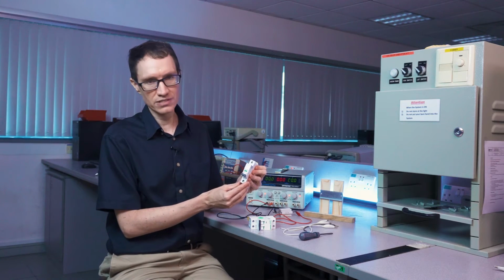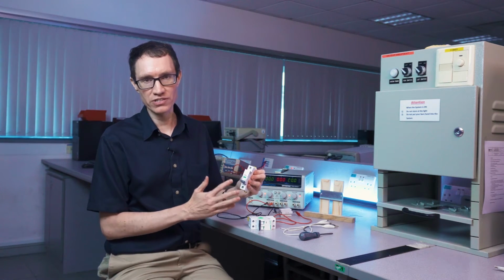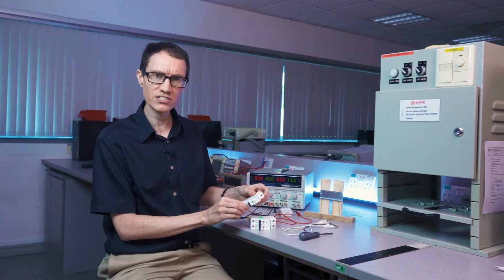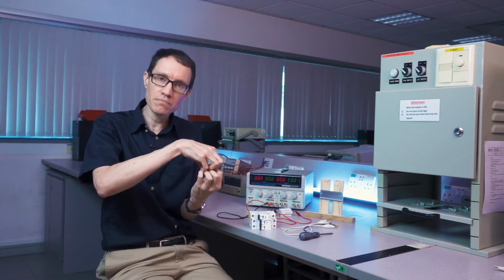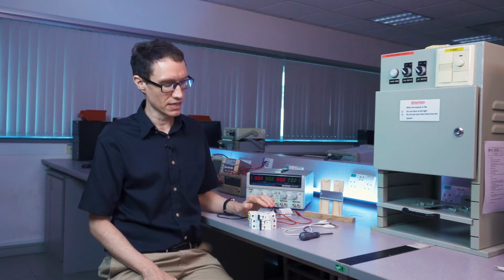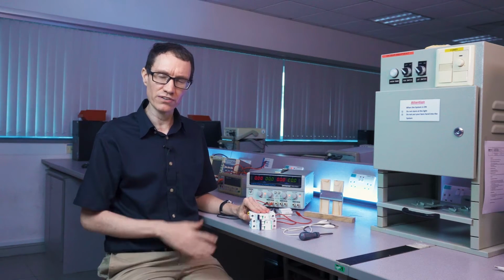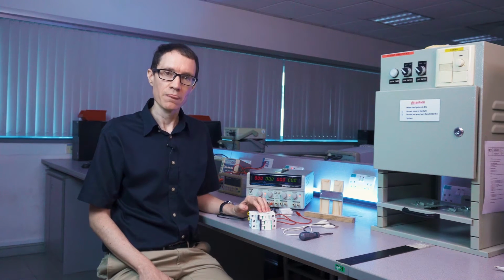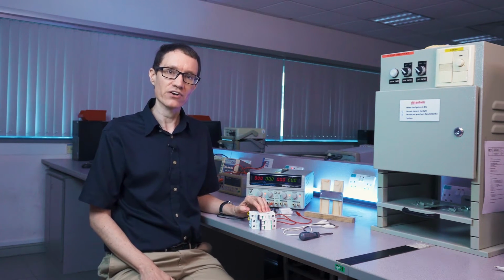If I try to, for example, send 5 amperes or 10 amps through this circuit breaker, it has a solenoid inside of it that will immediately pull the contacts apart. It will trip nearly instantaneously. But if I have just a little bit more current than the rated current, say 1.5 amperes or 2 amperes, the circuit breaker might allow that current to pass for several minutes before it trips because it has a thermal tripping mechanism for those lower currents.